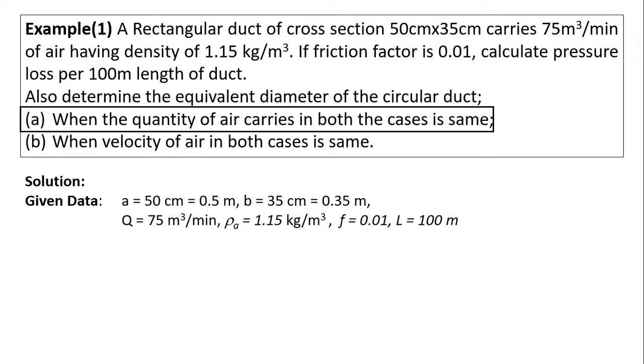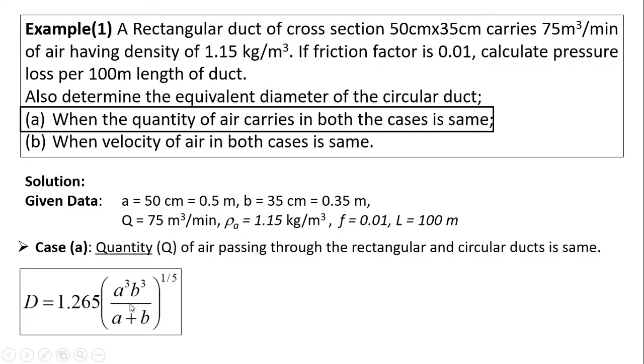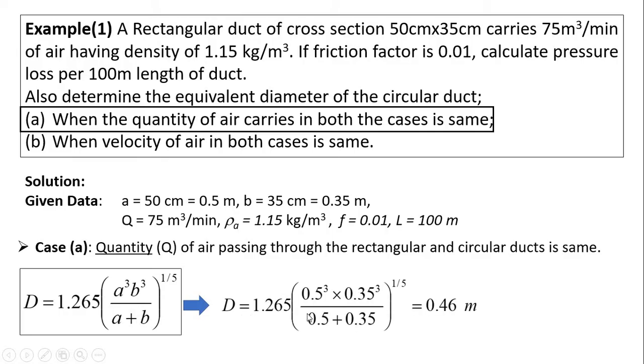Now we calculate the equivalent diameter of circular duct for two criteria. For the first criteria — when quantity of air in both cases is the same — we use the derived formula. Putting in the values of a and b, we get the equivalent diameter of circular duct D = 0.46 m when the quantity of air Q passing through rectangular and circular duct is the same.